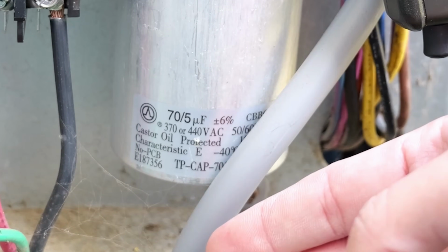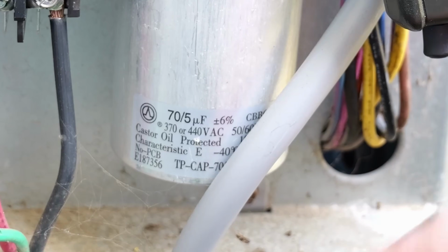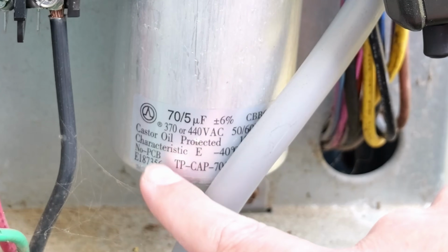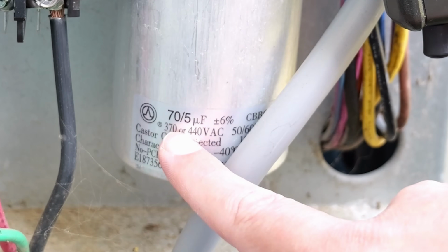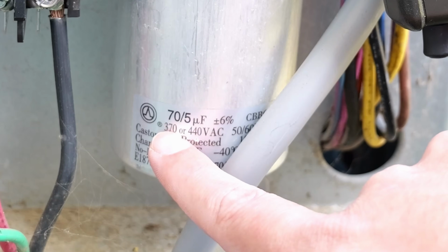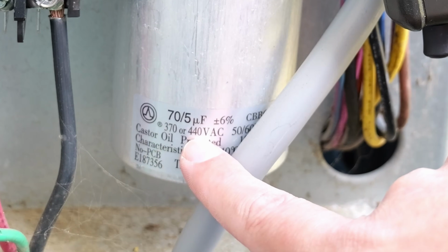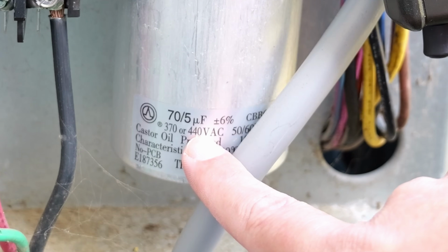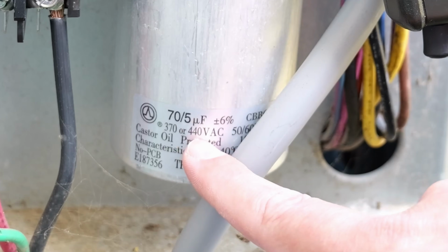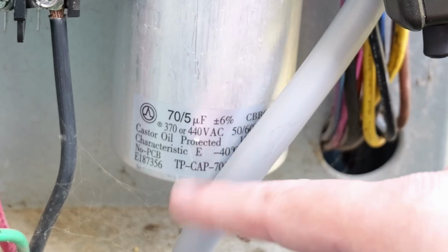All your capacitors are different. They're all going to say different readings on them. If you do need to replace them, make sure you're replacing them with the same size and same type. You also want to make sure on this one it says 370 or 440 volts AC. So if you are replacing them, verify the numbers, make sure you're getting one that is exactly the same.